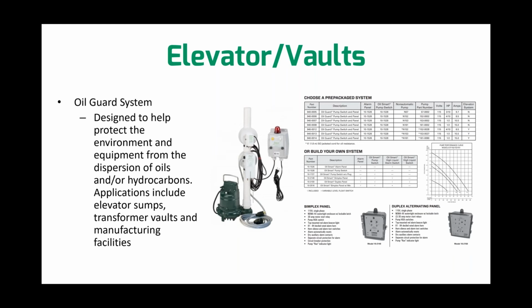One thing to note here is the way this is installed: the pump switch should be about 3 inches from the top of the pump. So what happens is if there is oil on top of the water, as it's rising up, that pump switch is not looking to sense that oil. The pump switch is only sensing the water to know when to turn on and turn off when water's in the system. If oil is in there, nothing's going to happen. It continues to stay on top there until it reaches, let's just say it reaches that alarm sensor, and boom, it hits that alarm sensor and it lets you know, hey, I have oil inside the pit. I need to get somebody out there, need to get that oil out of the pit.